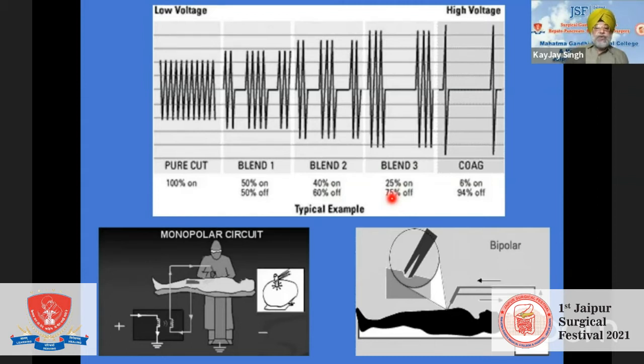The other thing which you need to know very, very clearly before you embark upon laparoscopic cholecystectomy is the direction of the current of the electrosurgical unit. Since we are usually using a monopolar circuit, a monopolar electrosurgical unit, in our laparoscopic cholecystectomy, this is the electrosurgical unit which you call cautery. It generates a current which is delivered by the pencil, that is the monopolar electrode, into the tissues, and that gets grounded by the grounding pad and back to the electrosurgical unit. This grounding pad is a very, very important aspect of laparoscopic cholecystectomy. Most of the problems of malfunction are related to this pad. I will come to it later.